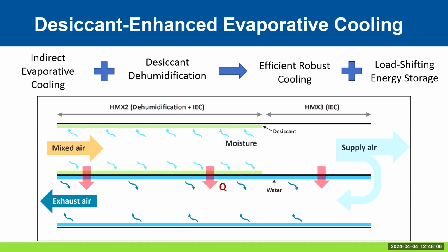In this system, by changing the flow rate of the desiccant, you can do more or less dehumidification, and by changing the split in the supply air between the wet channels and the supply, you can change how much you cool the air. So within a range, you have fully independent control of those. As for overall efficiency, if it's super dry and hot out, it'll operate like a really efficient indirect evaporative cooler.